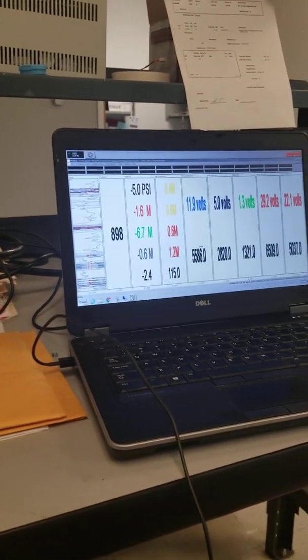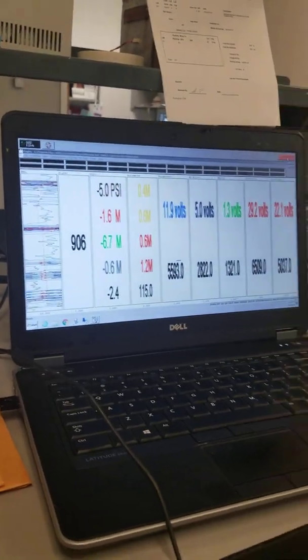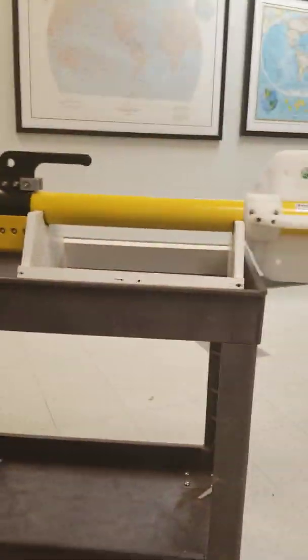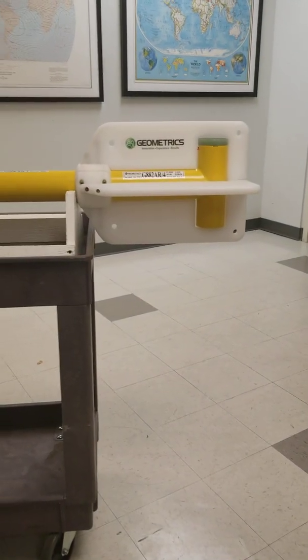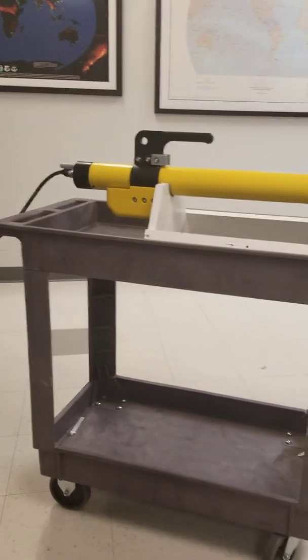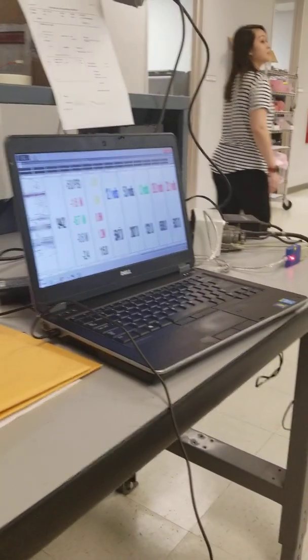Okay, so real quick recap. Diagnostic survey: verify COM port settings, make sure you have the instrument elevated off the ground, sensor oriented properly for your location, and sitting on something non-ferrous like a plastic cart, and then you should get some decent numbers, okay?